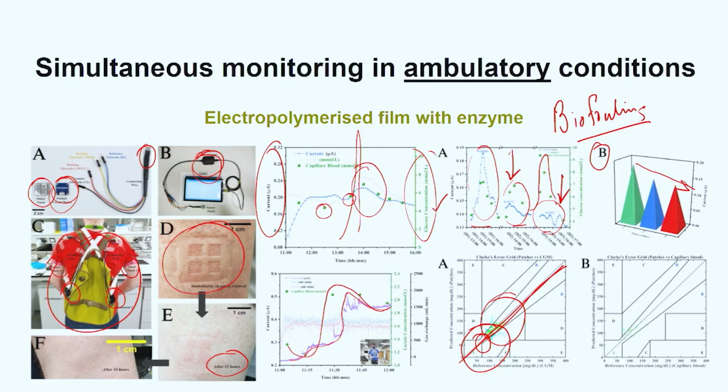So when you're developing a sensor for glucose, you have to be very careful, and you have to have a sensor that is very, very sensitive in this region of 2 to 4 millimoles, or below 65 milligrams per deciliter concentration. You can see here why it goes from wide towards narrow. That's how the whole zones are normally distributed. Zone B is moving parallel to A, and then zone C, zone D and zone E are quite outside. Anything outside this, if it's not an outlier, is totally unacceptable, because it can have a dangerous effect on the person who is being monitored. So this also tells you a little bit about the flexibility.